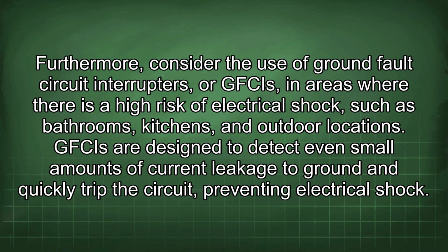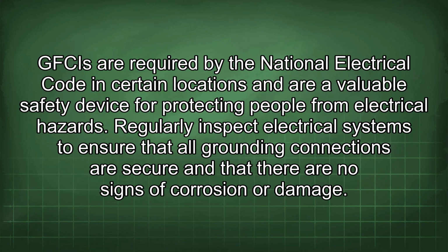Furthermore, consider the use of ground fault circuit interrupters, or GFCIs, in areas where there is a high risk of electrical shock, such as bathrooms, kitchens, and outdoor locations. GFCIs are designed to detect even small amounts of current leakage to ground and quickly trip the circuit, preventing electrical shock.